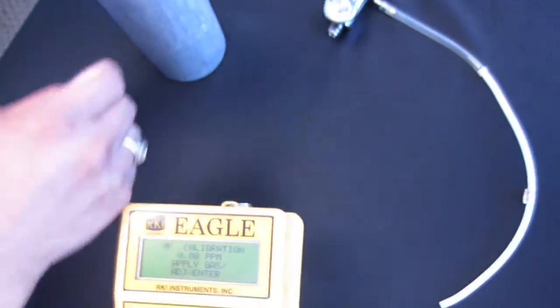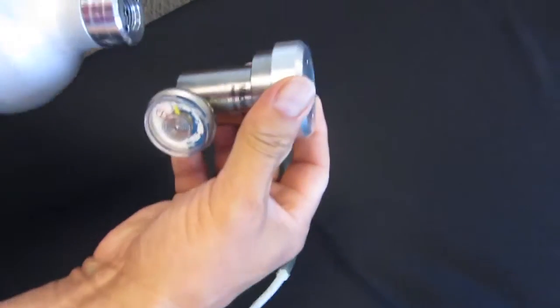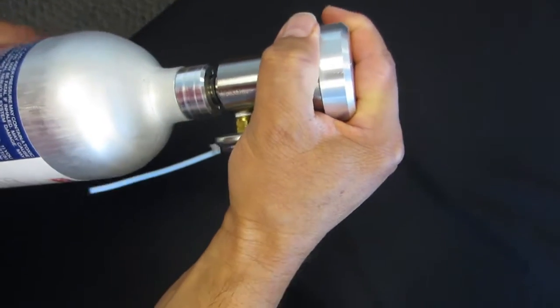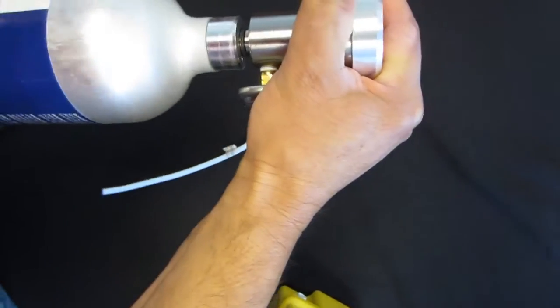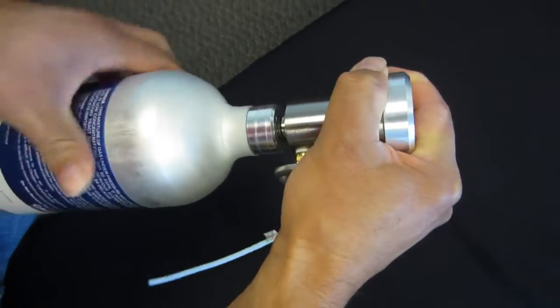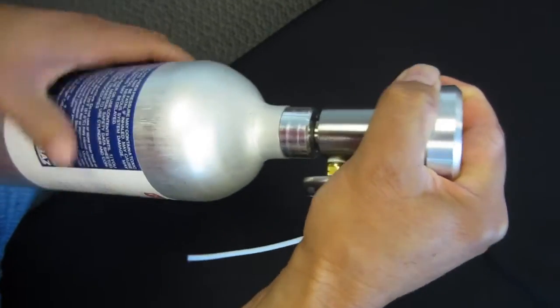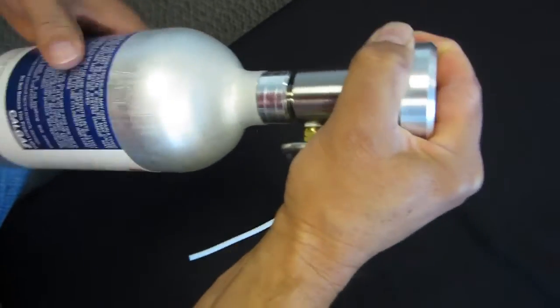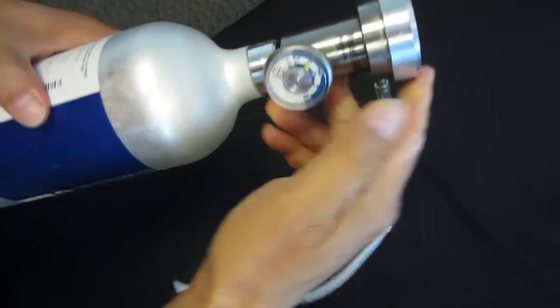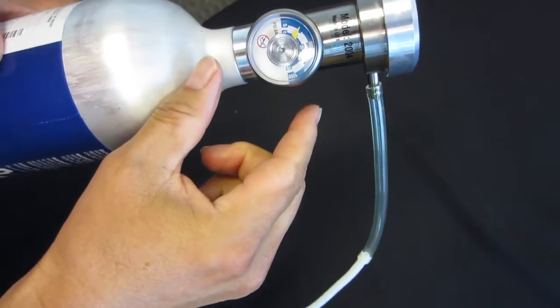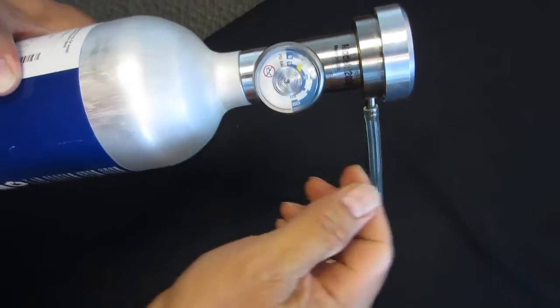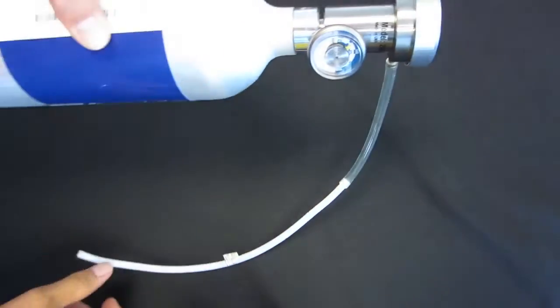So the next thing we're going to do is attach the regulator, this demand flow regulator, to a chlorine cylinder. And I'm just going to hold the regulator like so and slowly twist the cylinder onto the regulator until we're nice and snug. Okay. Pressure has come up on the gauge, so we know there's a good seat between the two pieces.